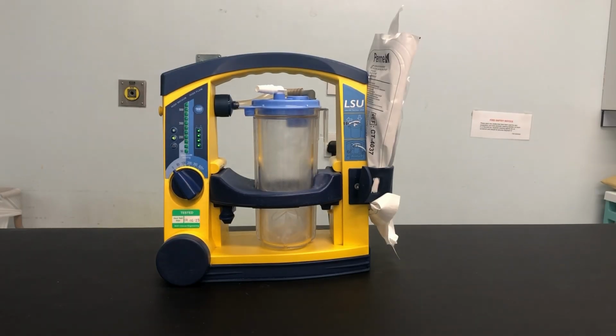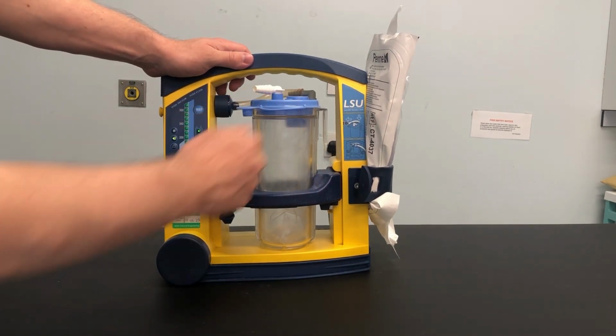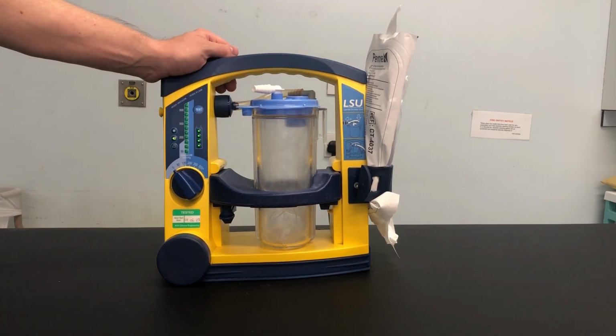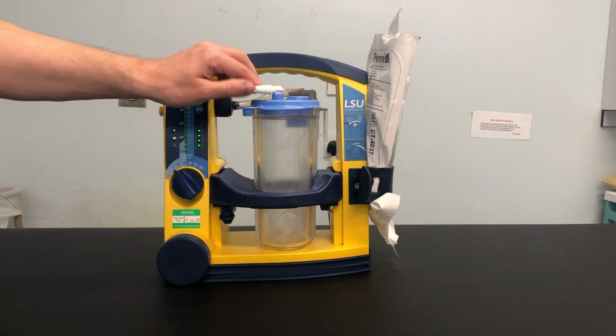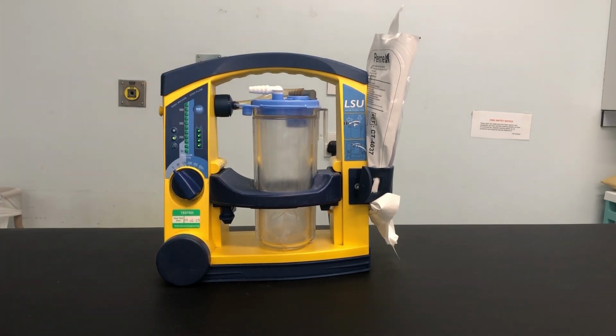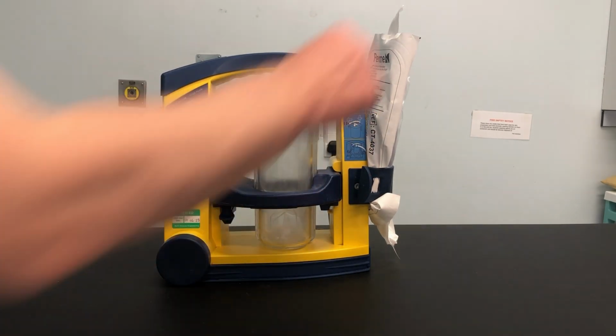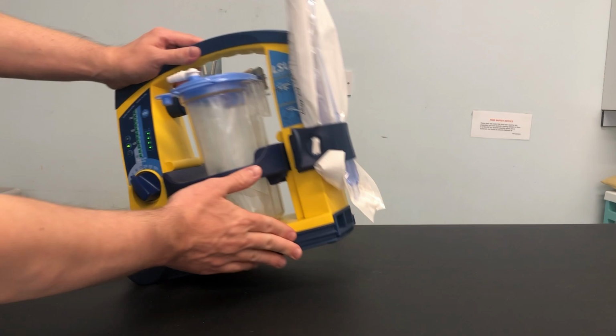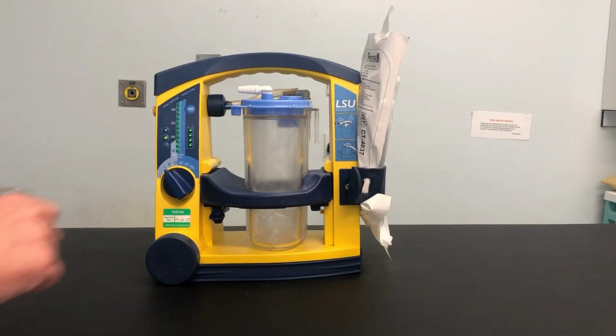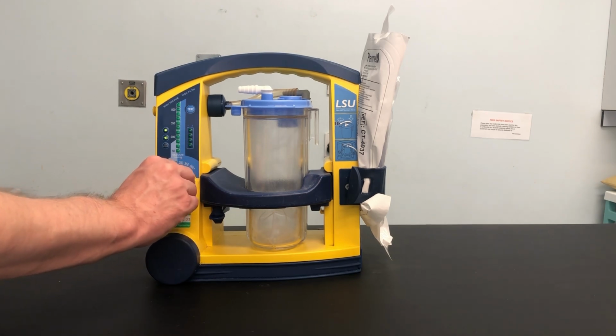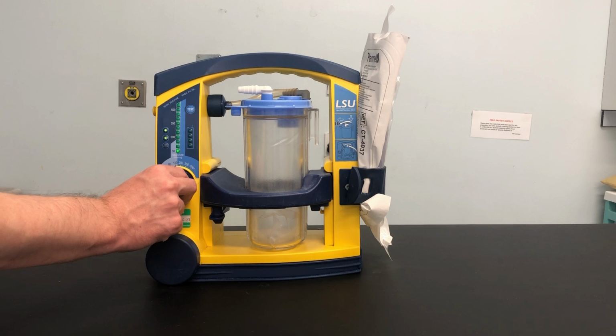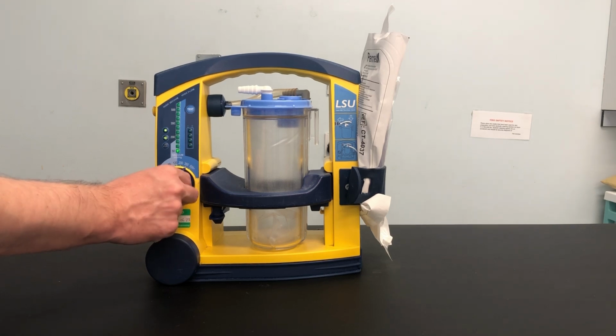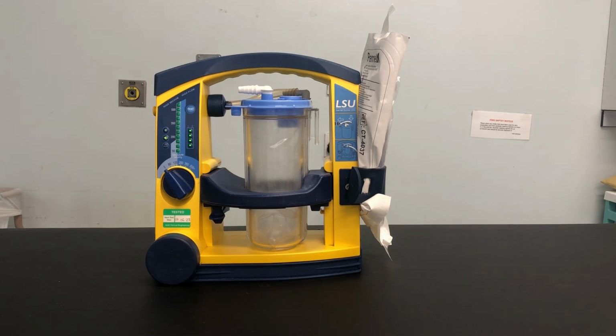So ensure that all the relevant accessories are available before it goes into use. You need the canister holder, vacuum tubing connector, and vacuum tubing if present, depends how old your device is. The disposable parts are the Serres suction liner and white angle connector, patient inlet, and the Serres suction tube. Also relevant, appropriate suctioning attachments like the Yankauer and sterile suction catheters. So, switching the device on and checking it's working. The LSU is switched on by turning the knob to the required setting. Each setting indicates the maximum achievable level for the selected position, i.e. 80, 120, 200, 350 and 500 plus millimeters of mercury.